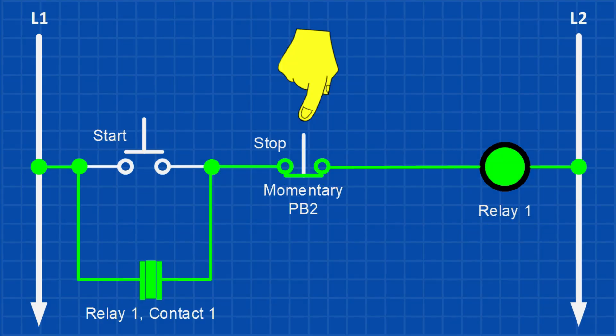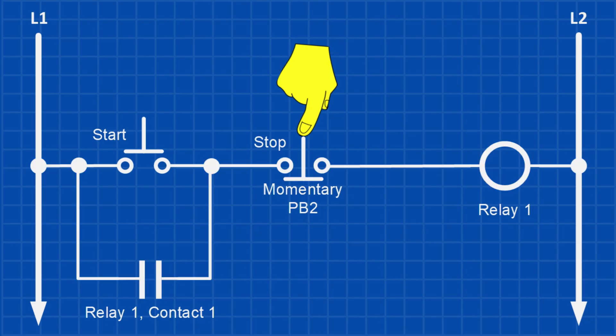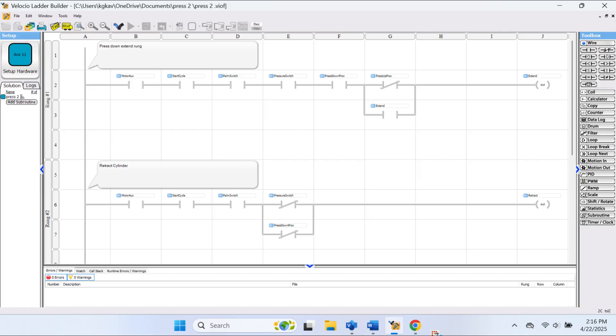Relay one stays energized, and to stop the circuit, we use a momentary normally closed stop push button. Once the stop push button is pressed, it breaks the circuit and relay one de-energizes. To turn it back on, you'll need to press the start push button again. Here, we are using relay logic to create a latch. But how would you do this in a PLC program? That is coming up next.